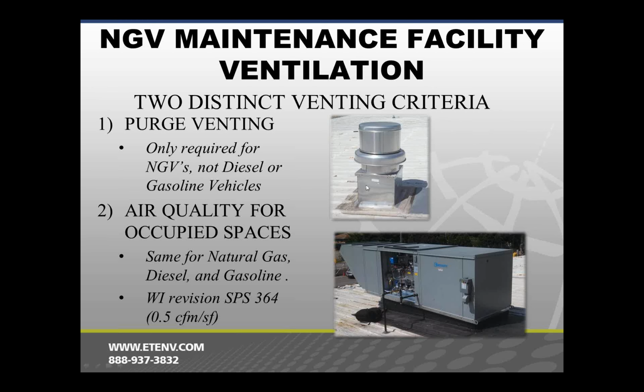So first off, on the ventilation, there are two distinct types of ventilation. One is normal occupancy ventilation, which is normally from the floor in a diesel and gasoline shop. This is where you want to remove your vapors from. But then we have the purge ventilation as well, to evacuate a natural gas event. And one note on the occupancy ventilation, you may have seen the other slides mention 0.75 CFM per square foot. Wisconsin's dropped that down to 0.5 CFM per square foot, and that's applied across the state.